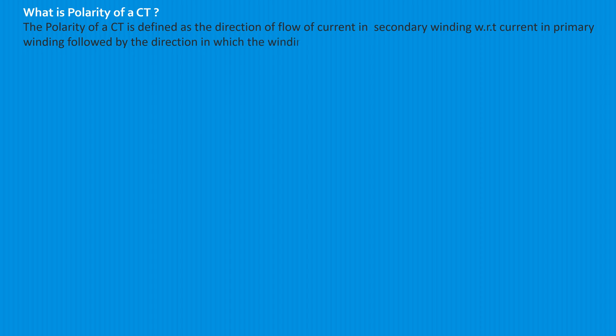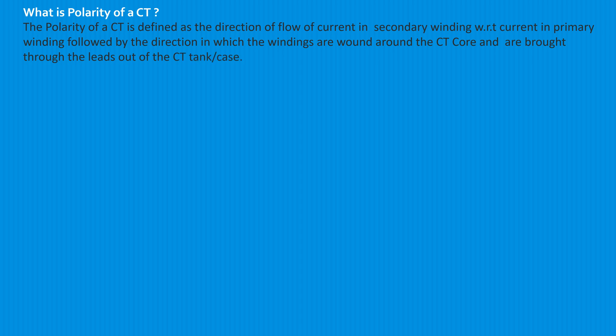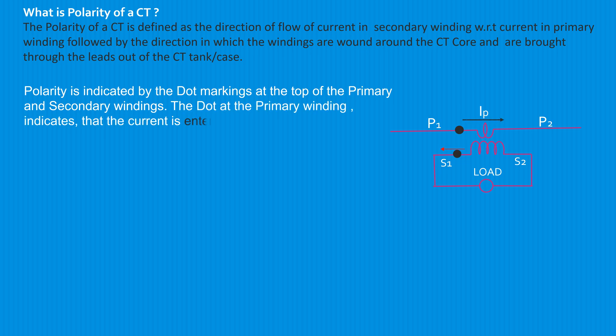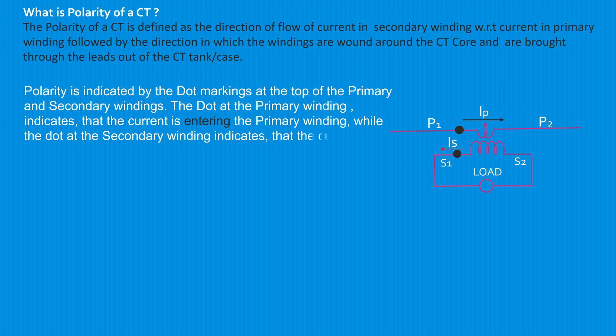The windings are brought through the leads out of the CT tank or case. Polarity is indicated by the dot markings at the top of the primary and secondary windings. The dot at the primary winding indicates that the current is entering the primary winding, while the dot at the secondary winding indicates that the current is leaving the secondary winding.